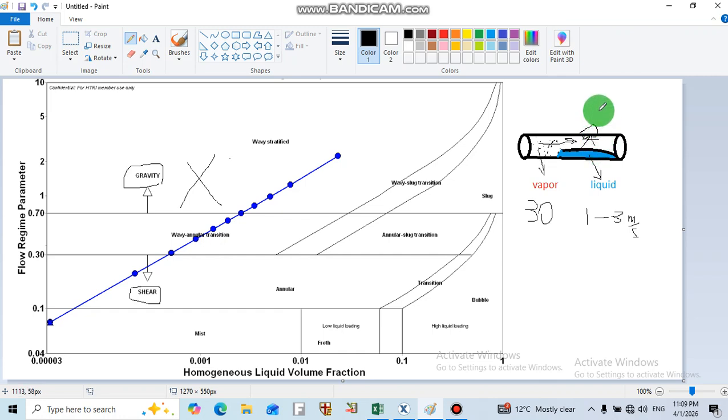So how can we address this issue? We have two ways. The first way is to decrease the length of this tube. As we decrease the length of the tube, for example, from one number to a decreasing number, we have less volume of liquid accumulated right here, and there is less probability of hammering that consequently vibrates the tube side of the shell and tube heat exchanger.